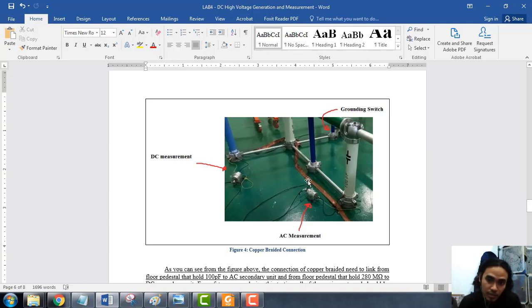We attach the measuring resistor, 280 mega ohm, for DC measurement. We need to connect the copper braided to the floor pedestal here, and also the DC secondary unit here. For advanced safety purposes, all of these floor pedestals need to be connected with the copper braided: the DC secondary unit, the AC secondary unit, the floor pedestal, and the grounding switch.